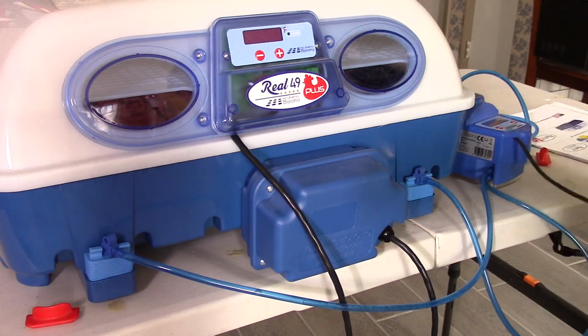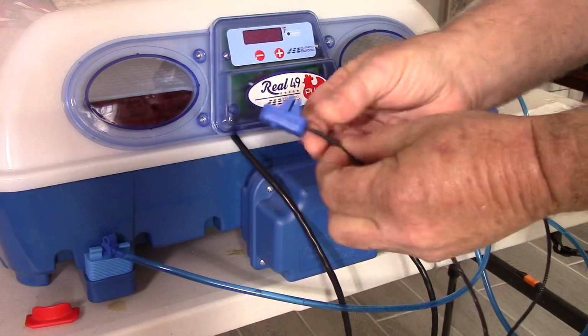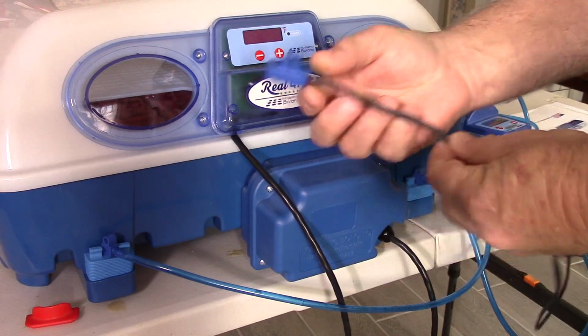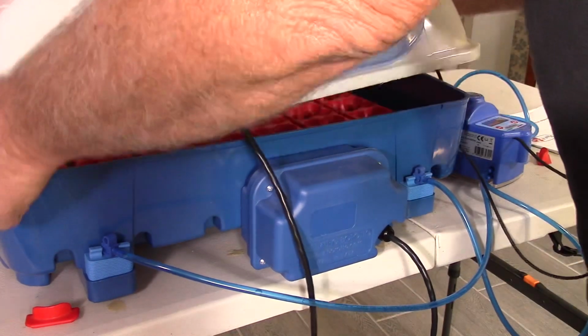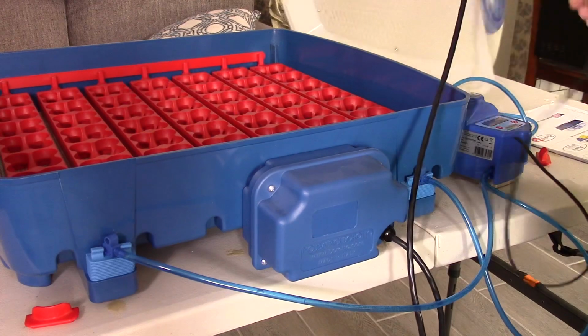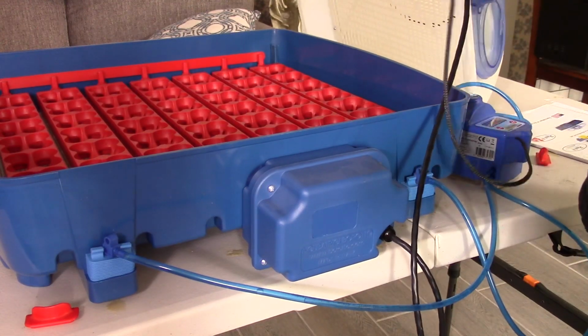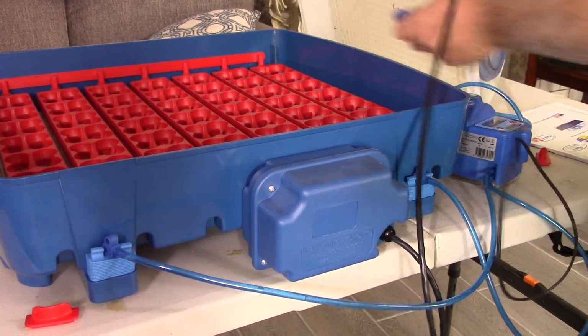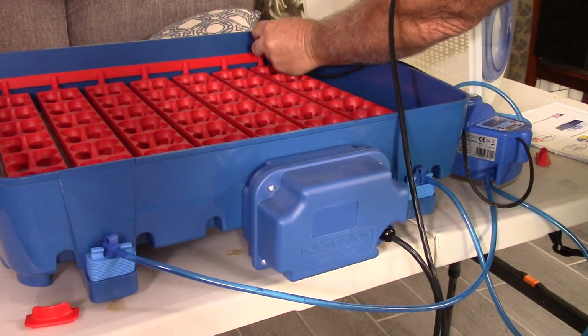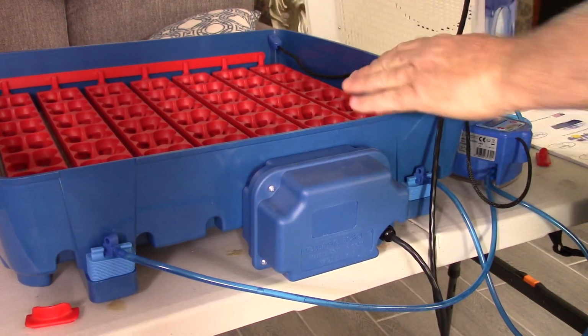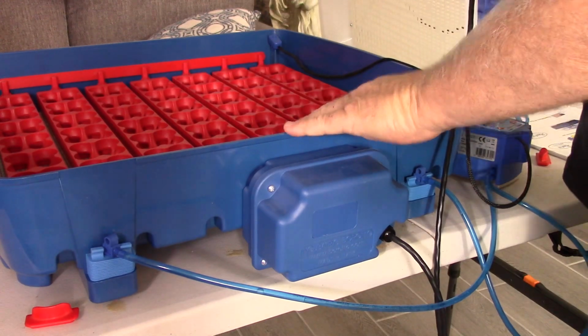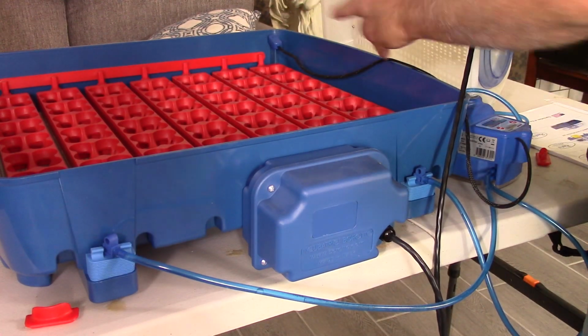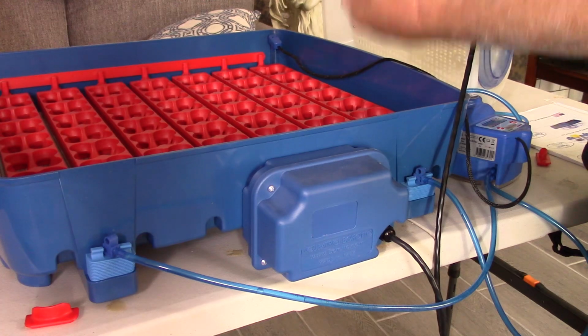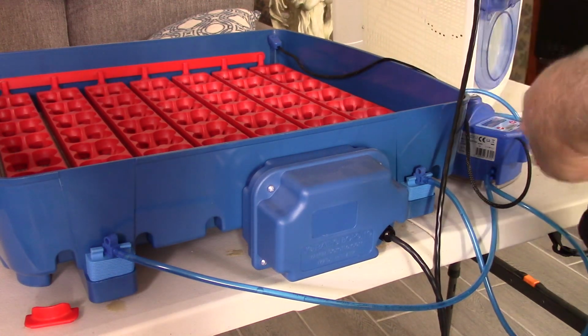The only other thing you need to hook up is the humidity sensor probe, and that goes in the back corner of the incubator. You do not want to hook it up to the front. You want it on the back. If you hook it up on the front, it's too close to these water ports and you're going to get a false reading. So set it up in the back, and that will give you a more accurate reading as far as humidity is concerned.